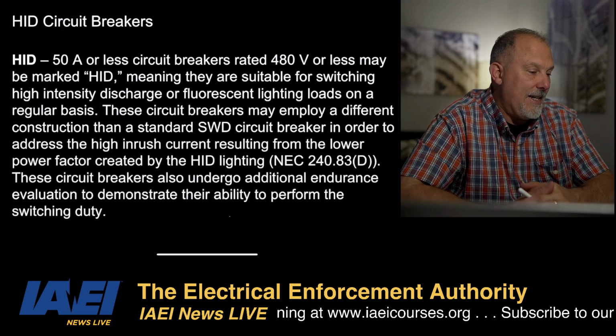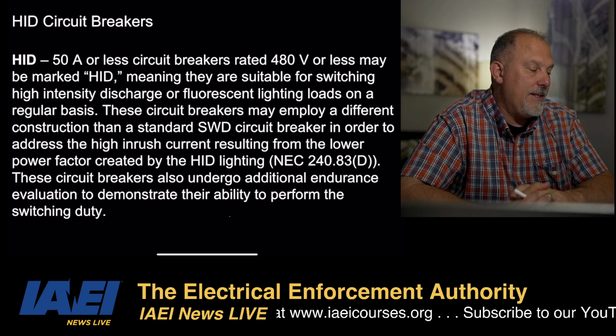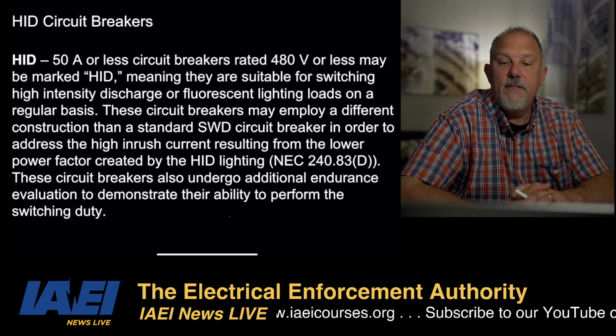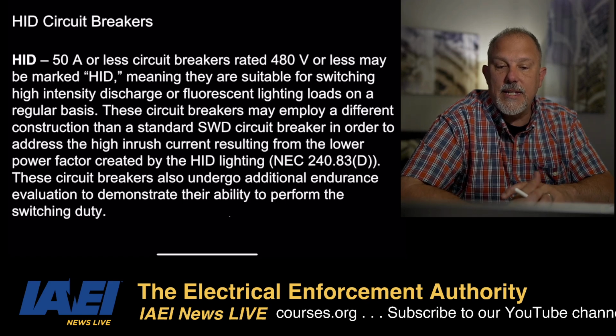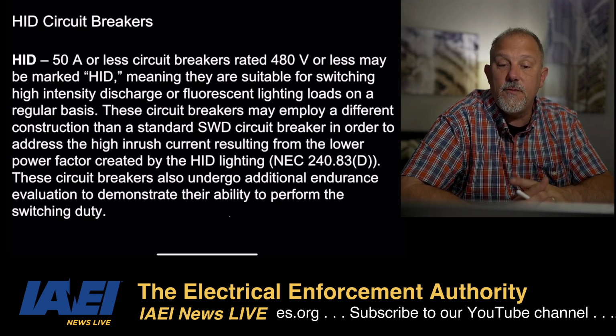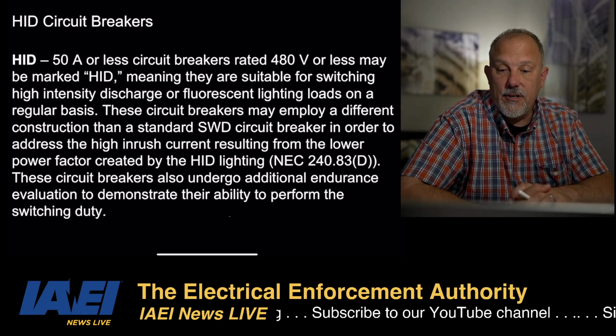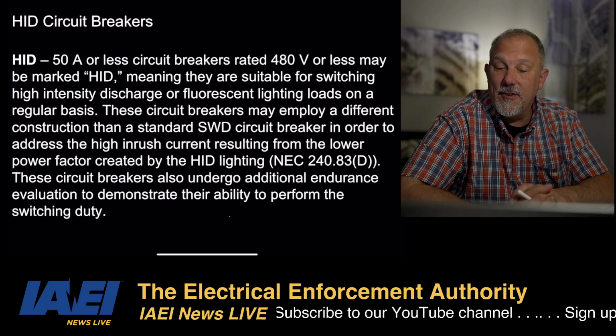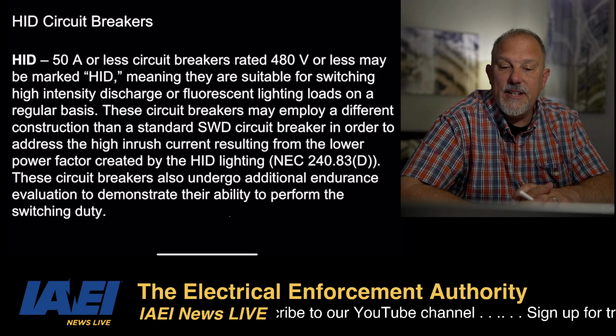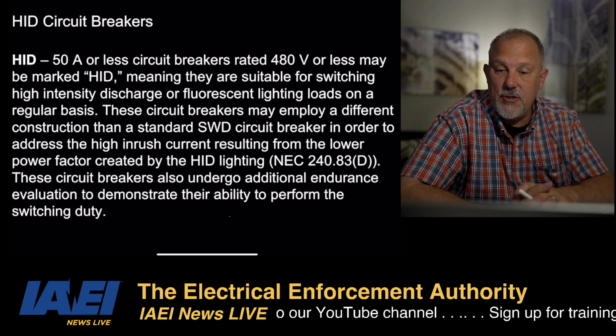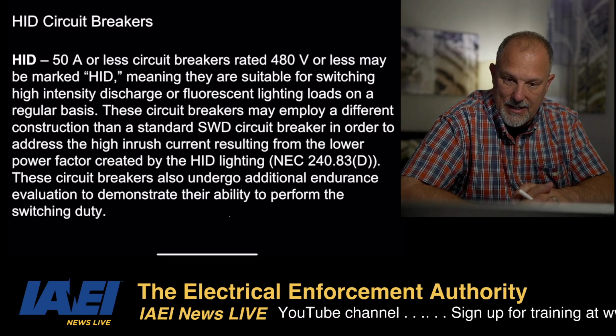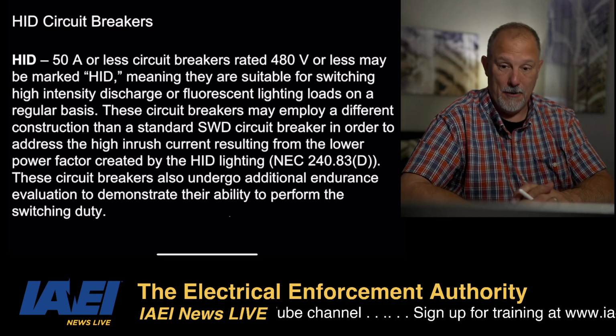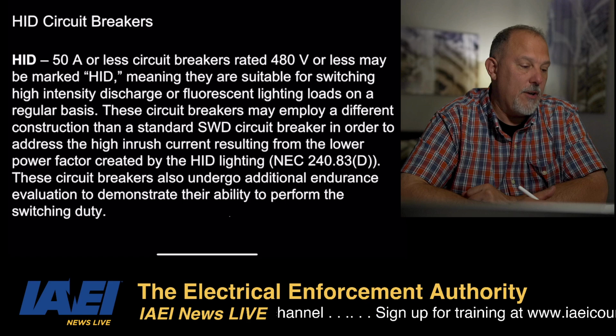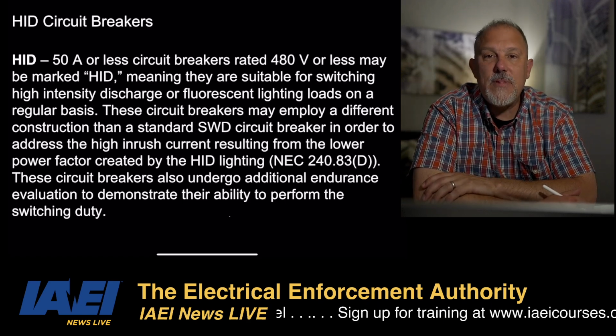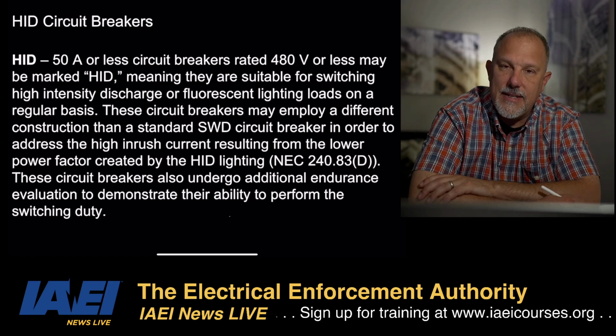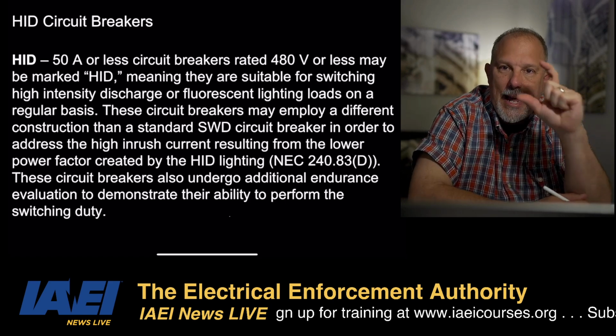An HID, so this is what it says. This is out of the standard. 50 amps or less circuit breakers rated 480 volts or less may be marked HID, meaning they are suitable for switching high-intensity discharge, fluorescent lighting loads on a regular basis. The breakers may employ a different construction than a standard switch-duty circuit breaker in order to address the high inrush currents. So, typically, what they're going to do here is we're going to have, in the standard, a different angle.